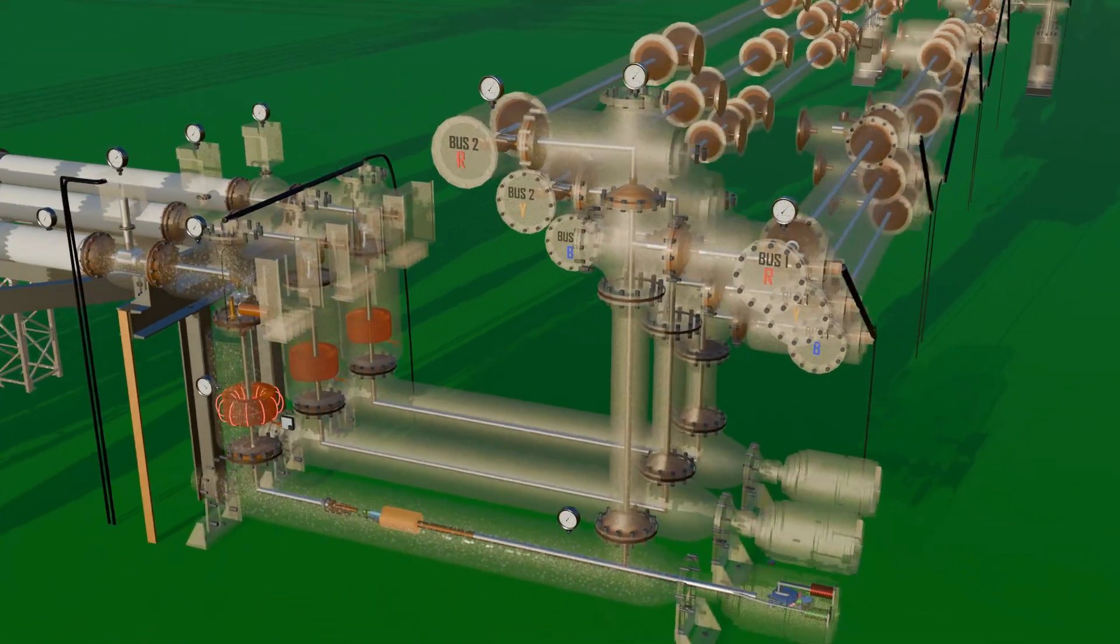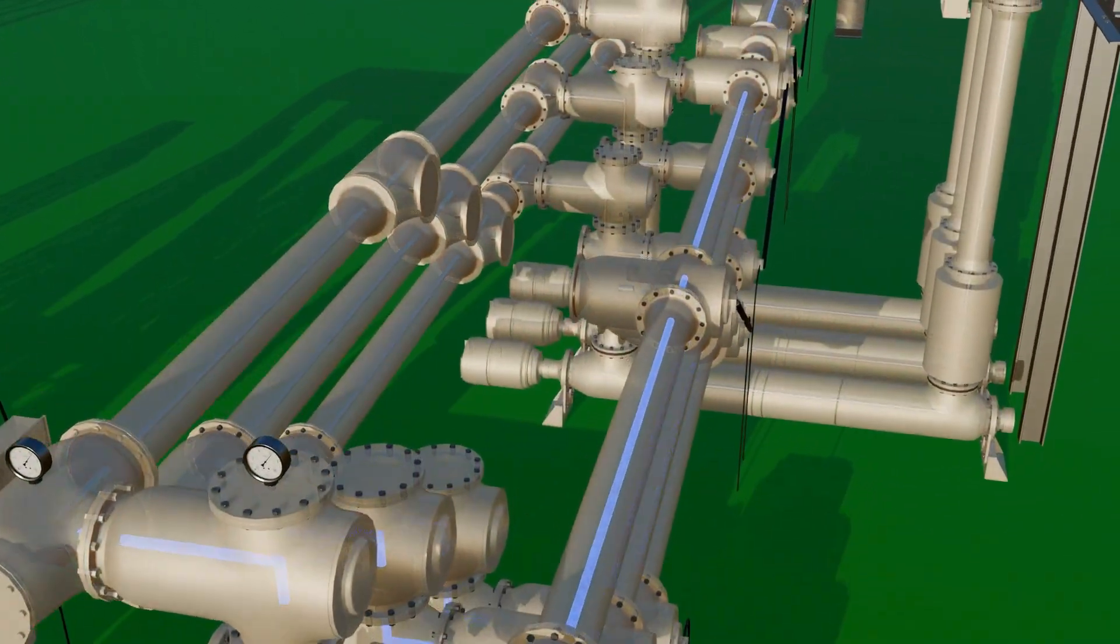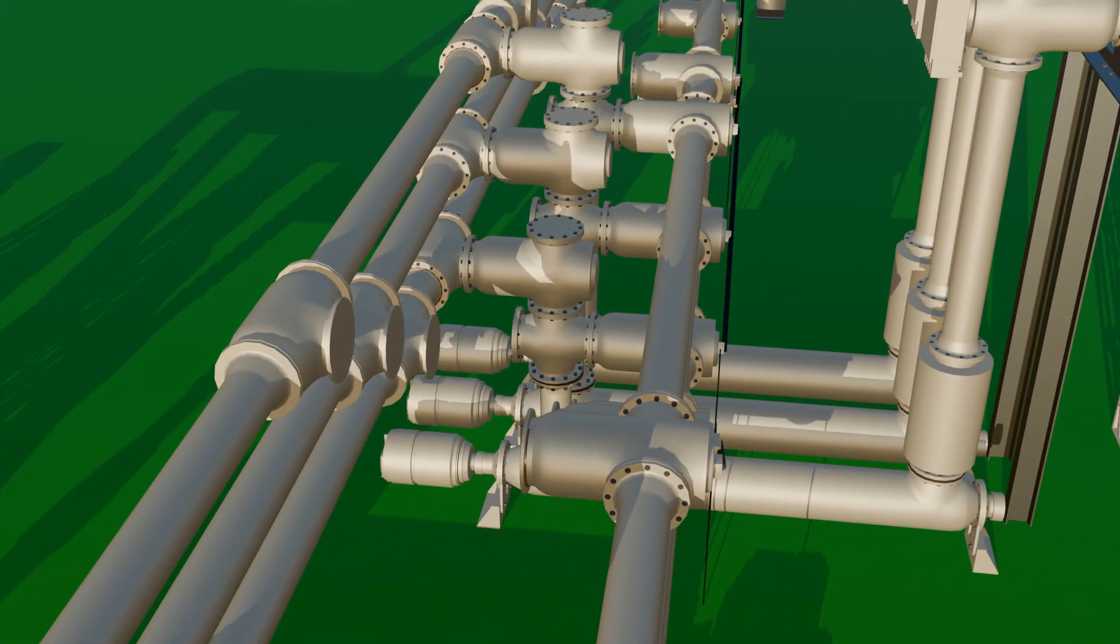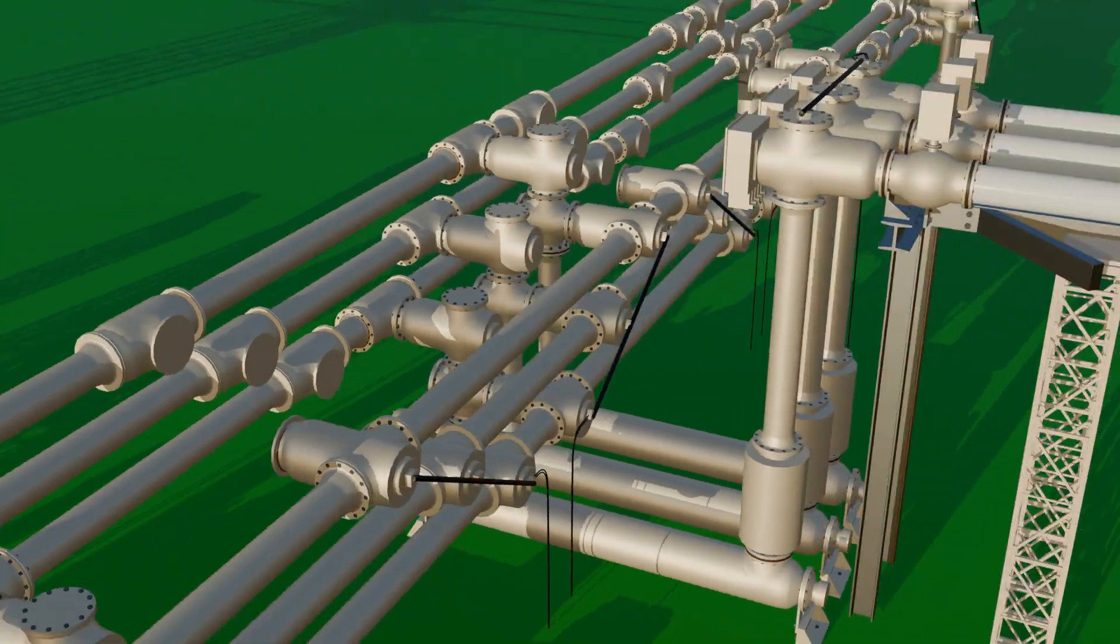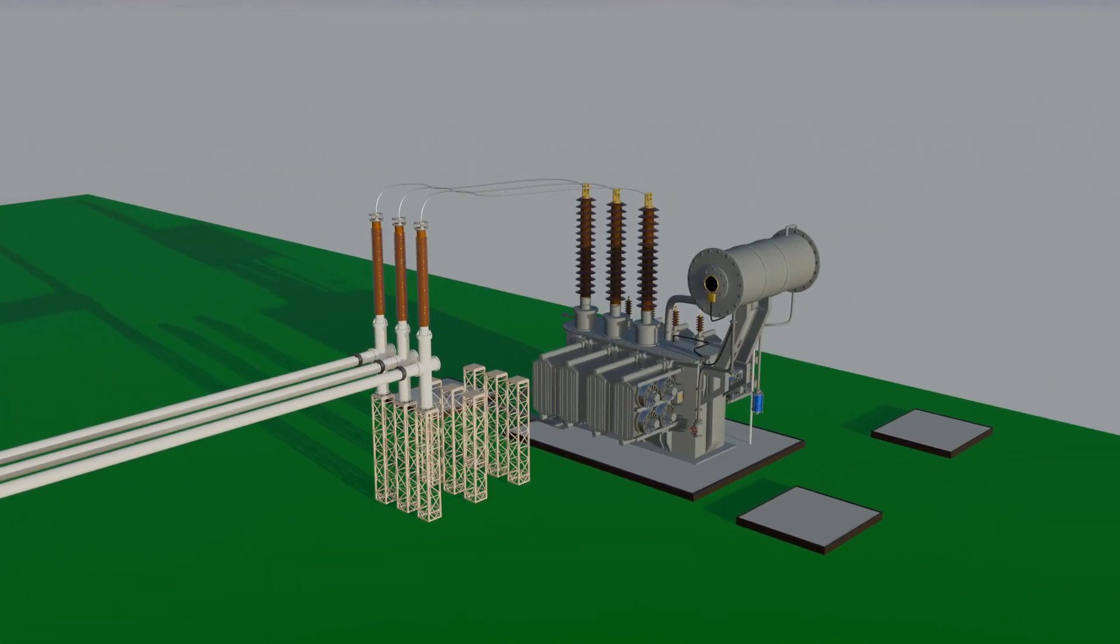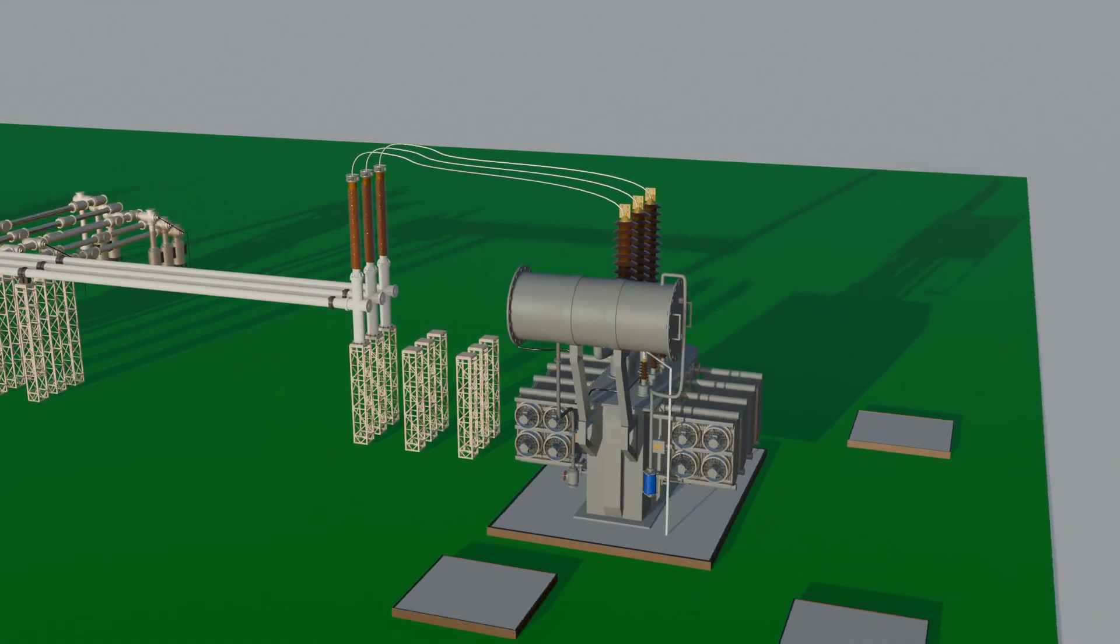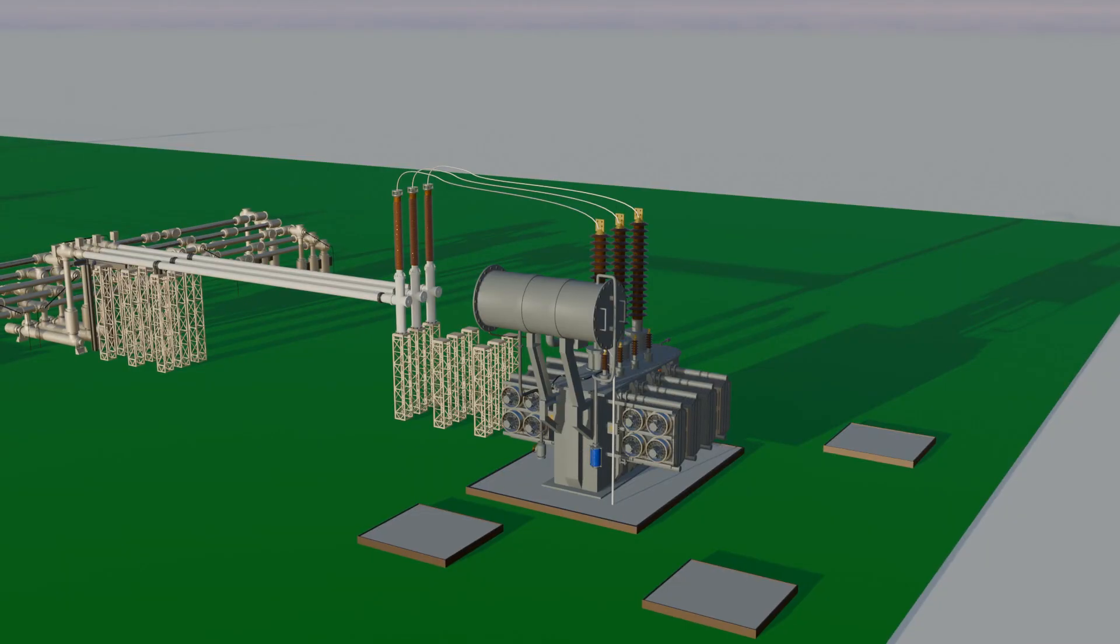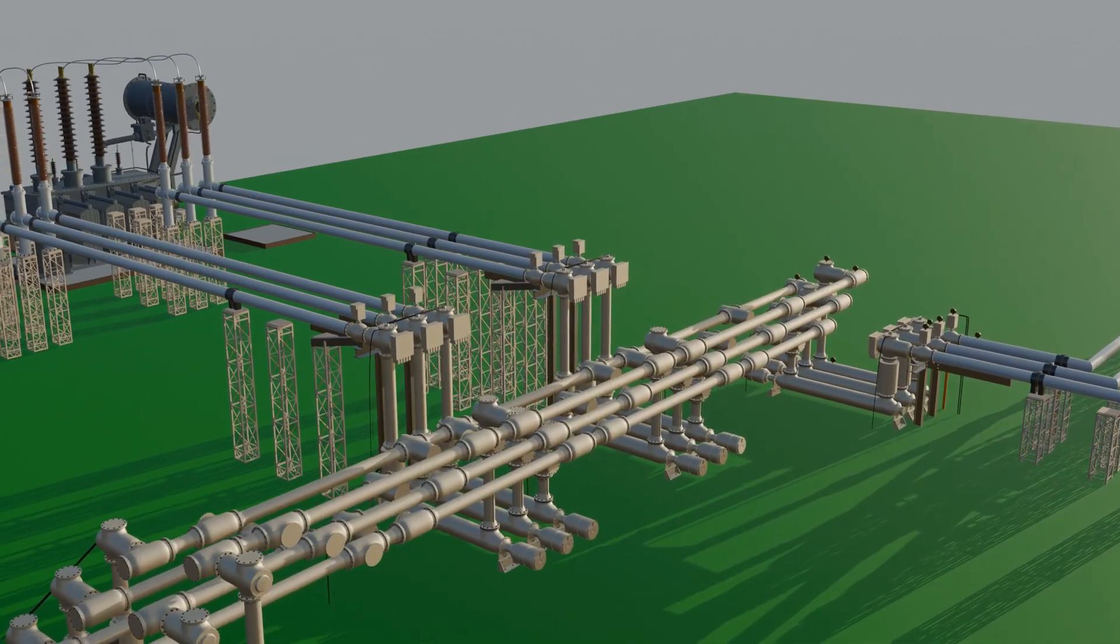For now, let's assume the main bus 1 is in operation. From the bus, multiple feeders are taken out. Each feeder has the following sequence per phase: isolator to current transformer to circuit breaker to isolator. From here, the feeder reaches the power transformer, which steps the voltage down from 440 kV to the required 220 kV or 132 kV. Similarly, multiple transformers can be connected to multiple feeders from the bus, allowing power to be transmitted to different regions.